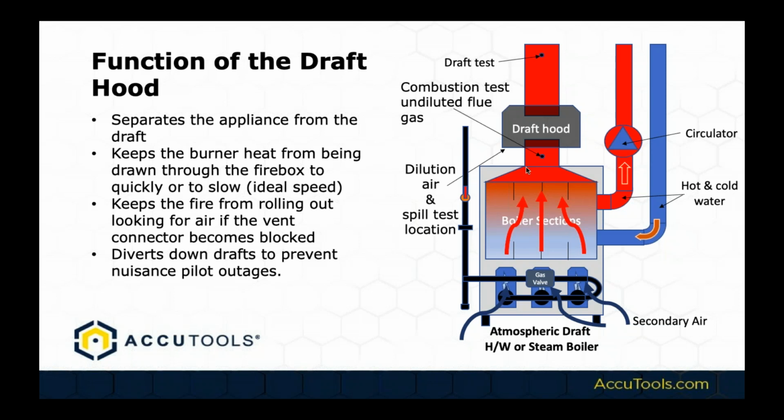And that draft hood's job is to physically separate the appliance from the draft, so that if that draft hood were to become blocked, like here where I've got a bird in a chimney, the flue gases would just spill into the space. Now, you might think, oh boy, that's something to be concerned with. But if an appliance is burning properly, all it does is produce carbon dioxide, water vapor, and heat. The typical reason we exhaust an appliance outside is because we don't want to take a chance of exposing anybody to carbon monoxide. And there's also a huge amount of water produced by combustion gases that would be hard for the home to handle. So it's really important that we exhaust those things outside.